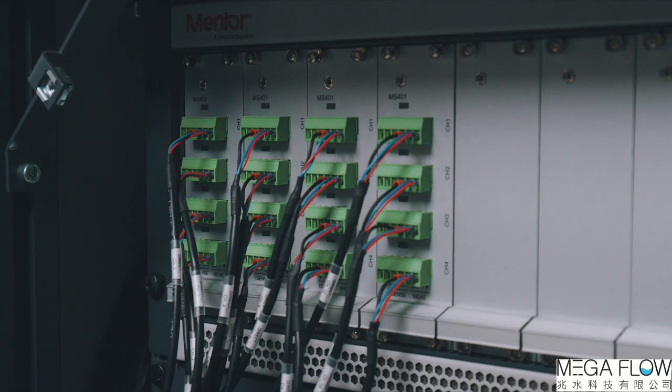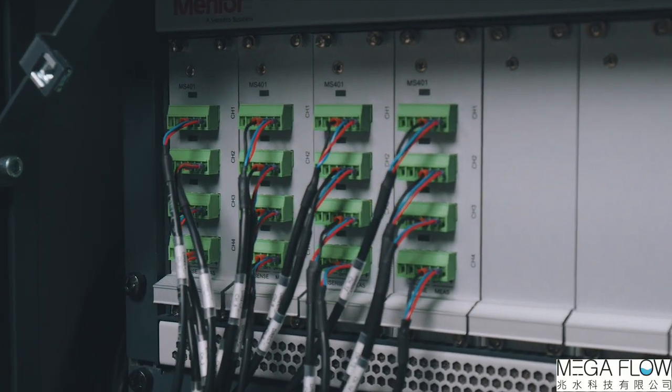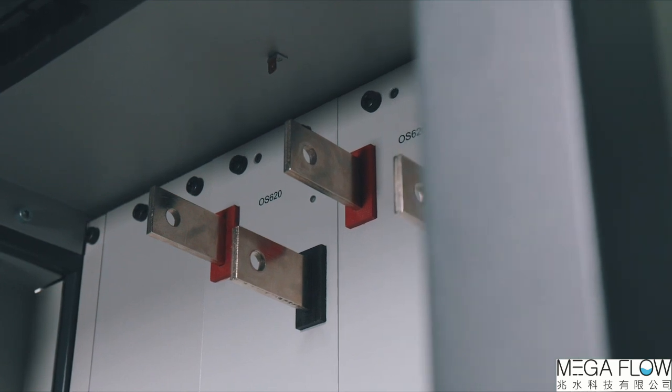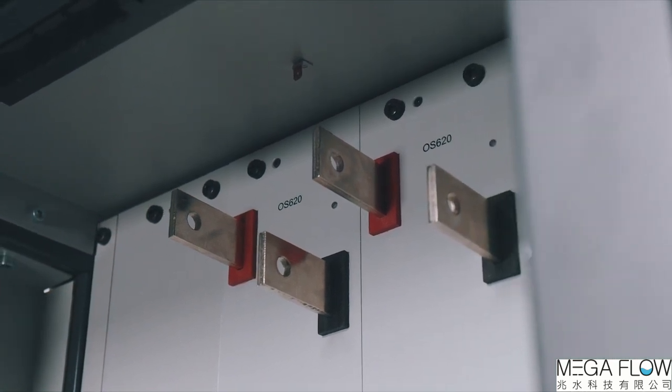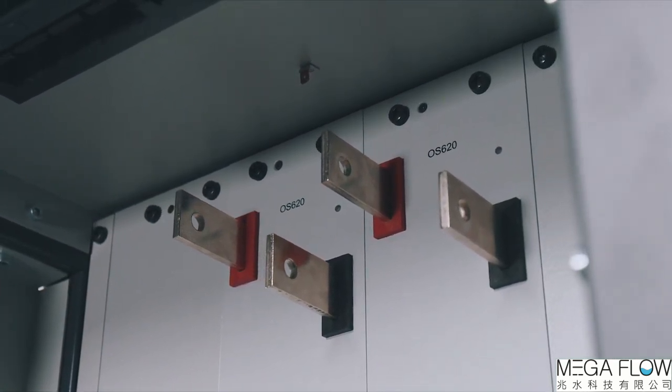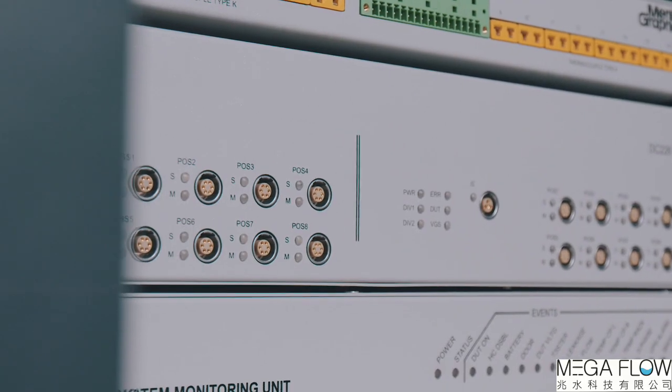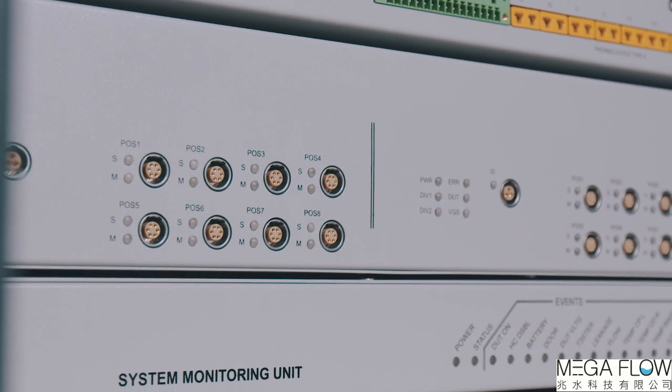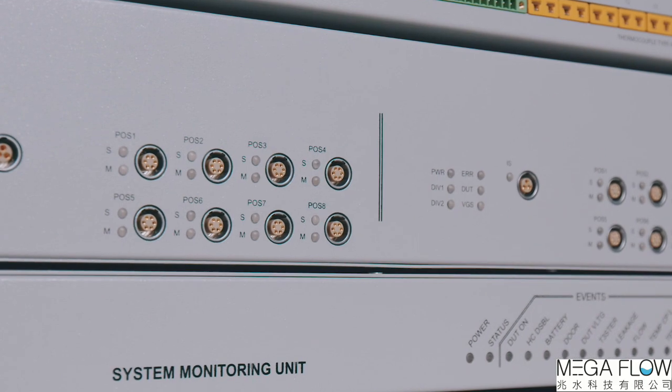The system is capable to test up to 16 devices, the shared heating current source alternately heating the two chains of eight components, making the system highly efficient and compact. Measurement current is available for each heating current output and dedicated gate drive output is available for all devices.